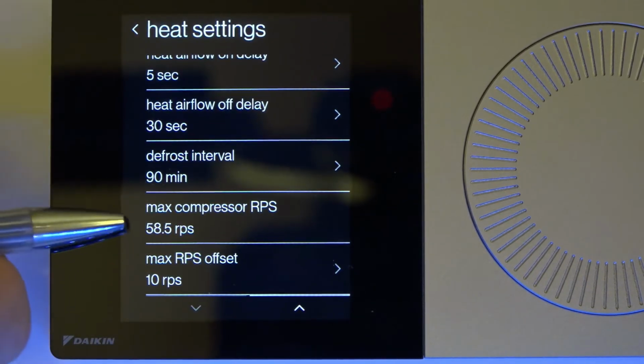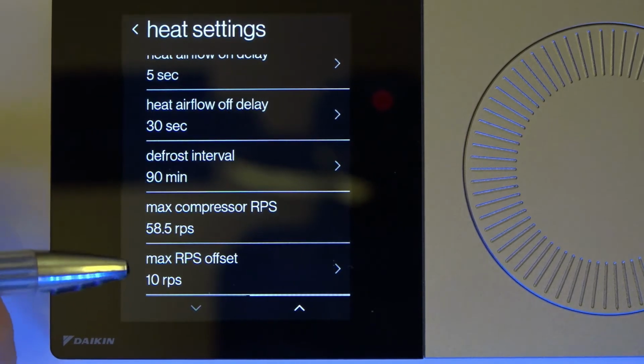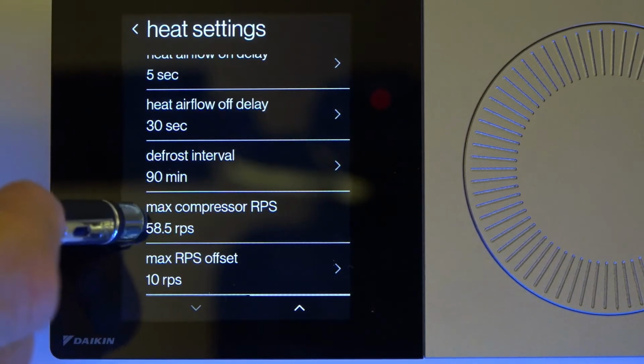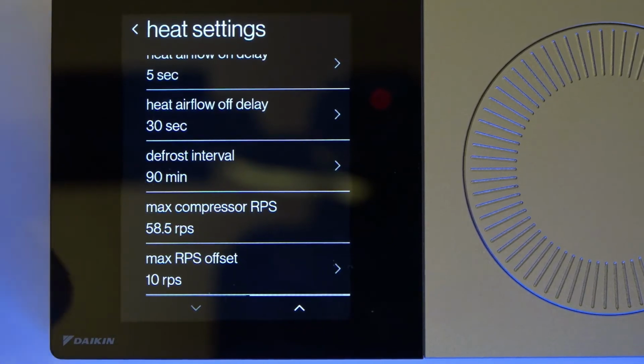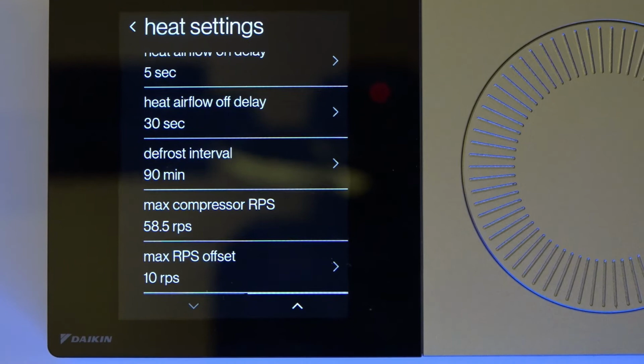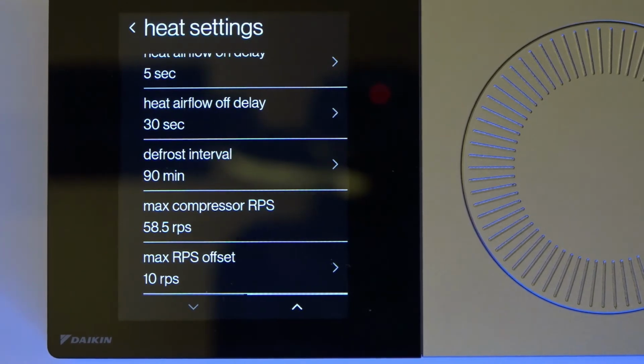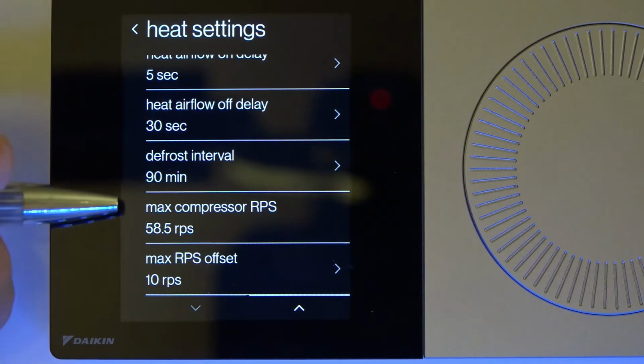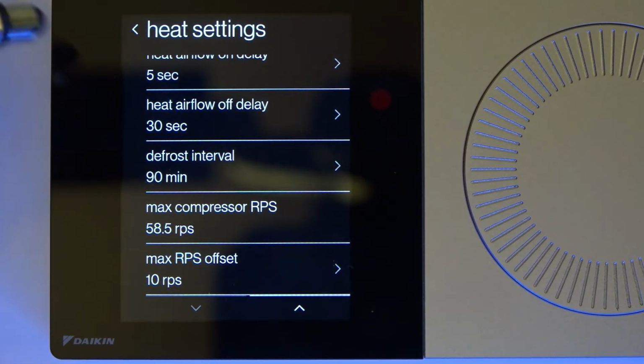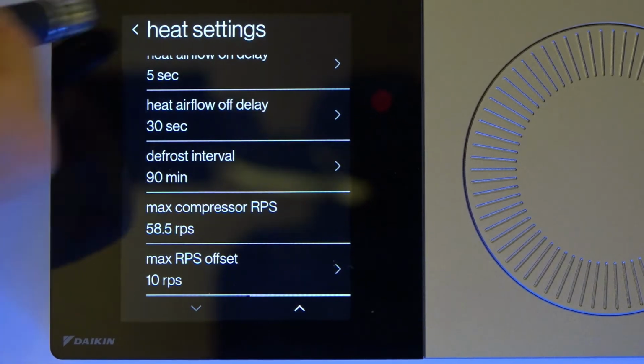And then, again, in heating, I've got my max compressor revolutions per second, and I can tweak it just a little bit. There again, this is a dangerous area here, and if you're not used to doing BTU calculations and also checking safeties, I recommend not fooling with this at all. Just leave it right where it's at.